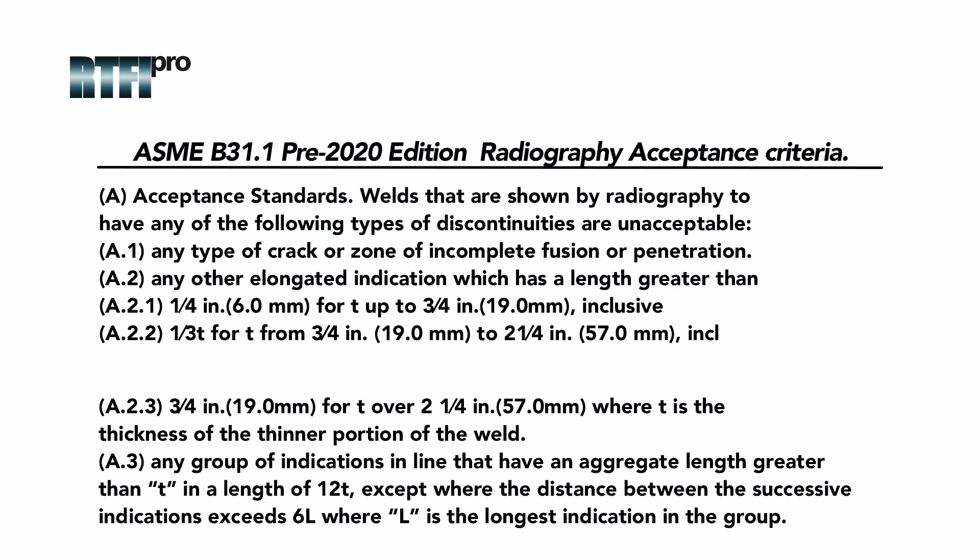A.2.2: 1/3t for t from ¾ inch (19mm) to 2¼ inch (57mm), inclusive. A.2.3: ¾ inch (19mm) for T over 2¼ inch (57mm), where T is the thickness of the thinner portion of the weld. A.3: Any group of indications in line that have an aggregate length greater than T in a length of 12T, except where the distance between successive indications exceeds 6L, where L is the longest indication in the group.